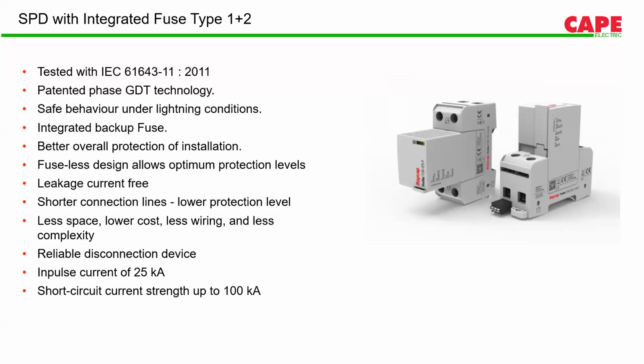So while selecting the SPD, of course, we have to select whether we need a type 1 SPD or a type 2 SPD. We have to see the voltage protection level. We have to see the location of the SPD. But in addition to all these parameters, with respect to safety, we have to see the short circuit current rating of the SPD. It is a very important parameter. So these integrated fuse SPDs have a short circuit rating up to 100 kiloampere without any additional backup fuse.